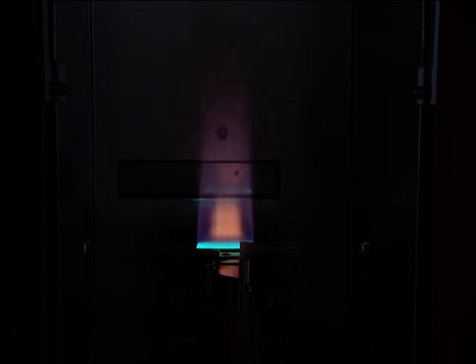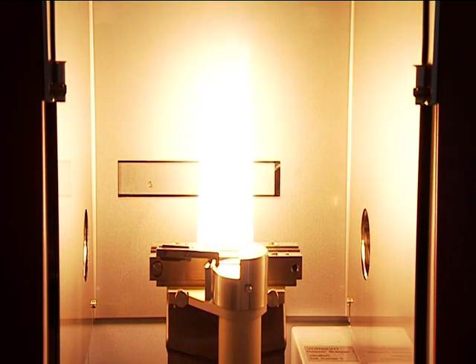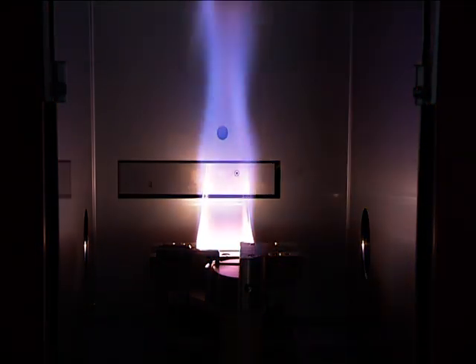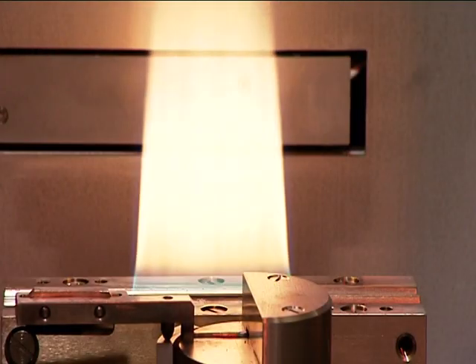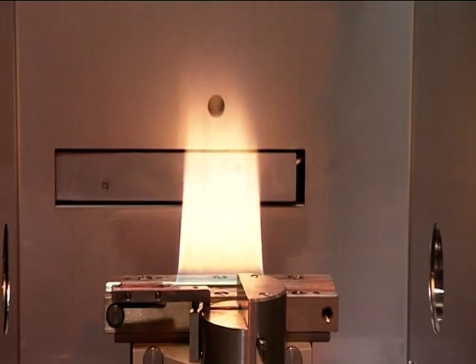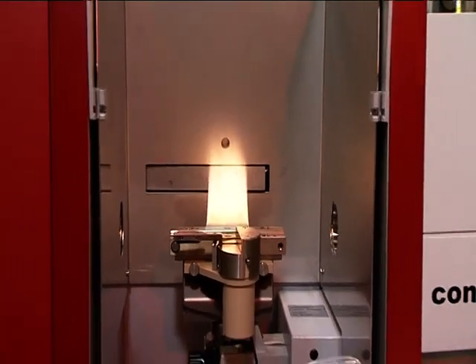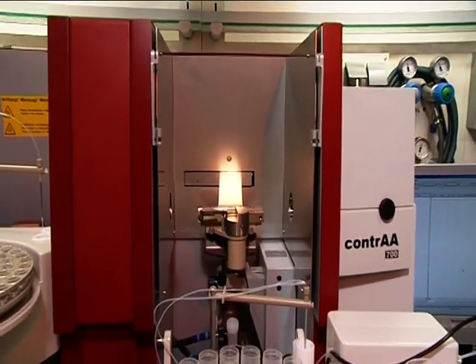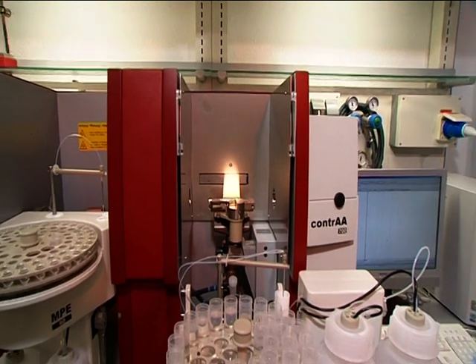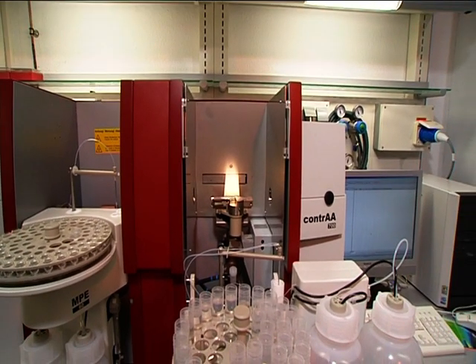The flame atomizer, which ensures trouble-free measurement even under the most difficult conditions, is distinguished by a high stability and efficiency. The materials used in the system are resistant to all chemicals used in analyses. The titanium burner head, with a slot 5 cm or 10 cm in length, is exchanged easily and recognized automatically by the instrument.